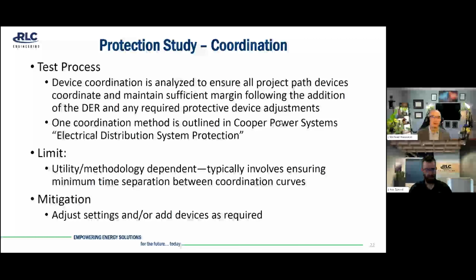Coordination. Device coordination is analyzed to ensure all project path devices are still coordinated and maintaining sufficient margin. One coordination method is outlined in the Cooper Power Systems Electrical Distribution System Protection, but it tends to be utility and methodology dependent as far as approach and then the limits that are applied. But typically it involves ensuring the minimum time separation between your coordination curves and then adjusting settings or adding devices as needed to maintain those coordination requirements.